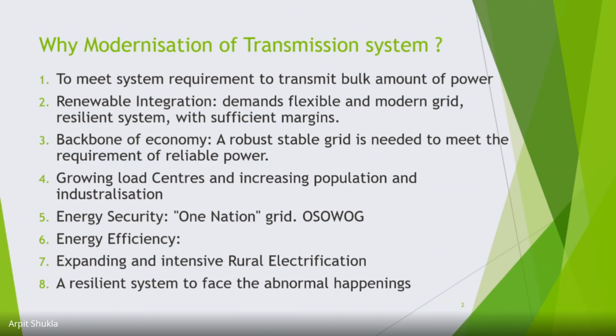It's a common experience, documented by standard authors, that if you do reconductoring of the distribution system, you first have to dismantle it, then lay another type of conductor, and your support structure may not be capable. So it's better to build slightly higher capacity from the start, so utility engineers don't face problems in the future.